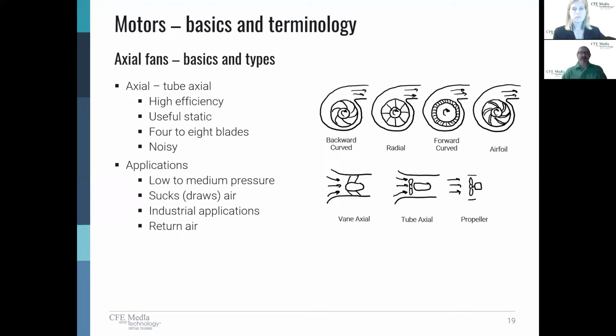Now, I see these a lot in returns. So if I have an air handling unit that I'm trying to squeeze inside of a space, and I can't fit those extra return section modules, what I could possibly do is take a tube axial fan, hang it from the structure, and now I have my return fan that I can control just the same way you control any other fan. So they provide a useful opportunity. Now, as noted, they're typically going to be drawing in air, which makes them good for not only returns, but also exhaust applications.